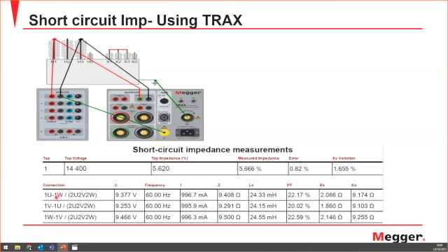For example, here 1UW is written as in IEC, while the connection here is actually showing ANSI, or American Standard. So it's the same, just a different standard between the result shown here and the connection. So UW, which is this part, and VU and WV, the three-phase results here. We have the Z, and from the current and the voltage, using the formula I showed before, we can calculate what we call the measured impedance here. We compare it with what's written on the tap impedance from the factory test that has been done before. We can see 0.82, which is less than 2% between the measured impedance and the tap impedance, which is good, as the standard says this has to be less than 2, and we are good at that. And even the XS variation, which is this one, we have very, very low variation also.